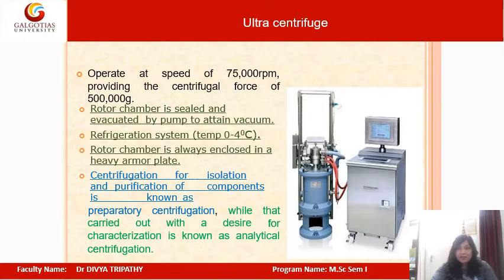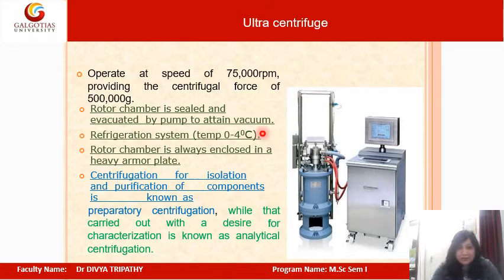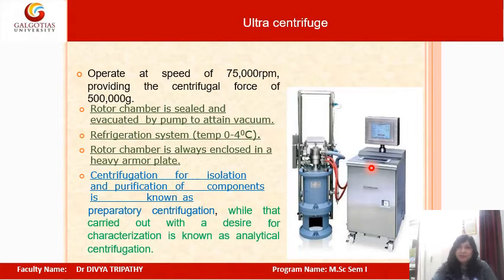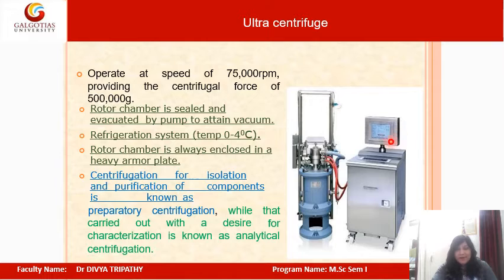Ultracentrifuges are very efficient compared to desktop and high-speed centrifuges. They can operate at speeds of 75,000 RPM and may provide centrifugal forces of 500,000 G. The rotor chamber is sealed and evacuated by a pump to attain vacuum. A refrigeration system maintains temperature from 0 to 4°C. The rotor chamber is enclosed in a heavy armor plate. These centrifuges also have a hardware unit associated with a software system, allowing input of different RPM or RCF values.